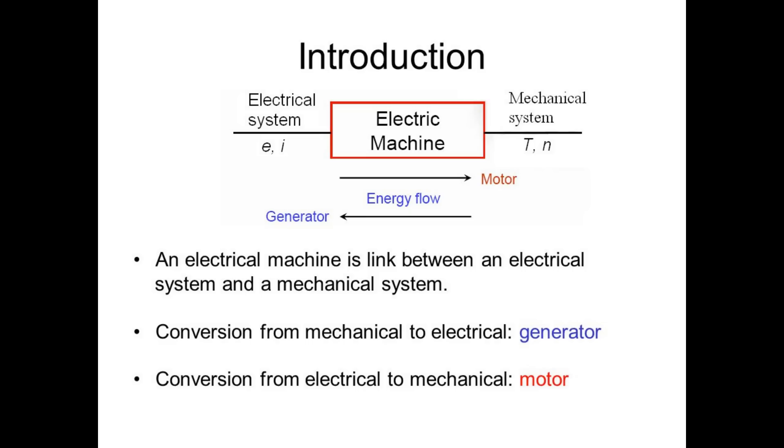The amps, the amount of push—you have to remember that a generator is a machine that takes mechanical energy and converts it into electrical energy. If you want more electrical energy out, you have to put more push in. There are mechanical limits to things. If you need to push too much out and your axle isn't thick enough, you can't put any more mechanical energy in and you'll break the machine. Those are the limits that limit amps. The build of the machine and the amount of force you can put into the machine limit the amps. The machine design itself—the length of the wire, the strength of the field, and the speed at which it turns—limit the voltage.